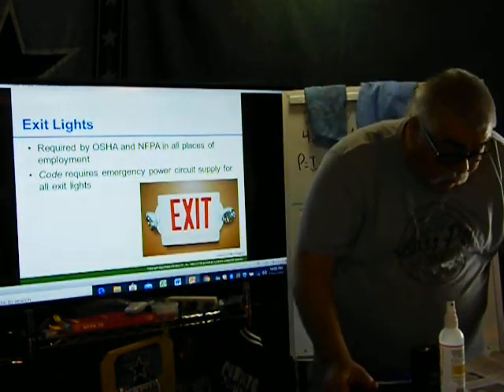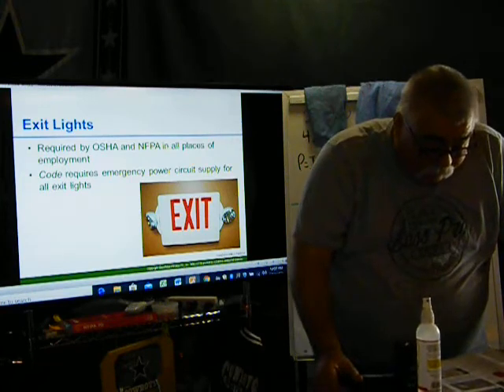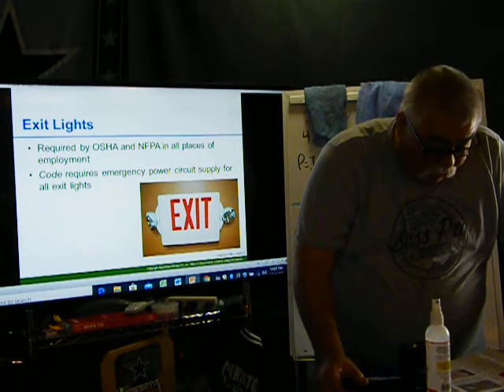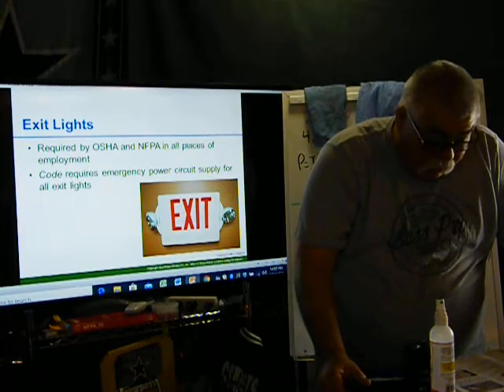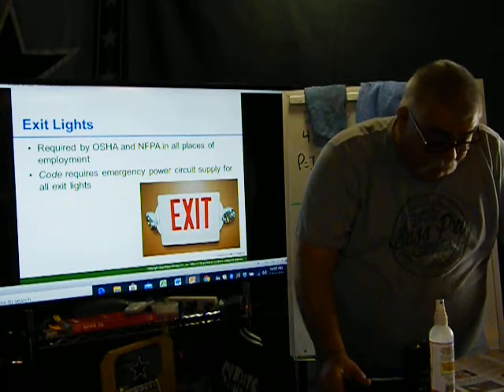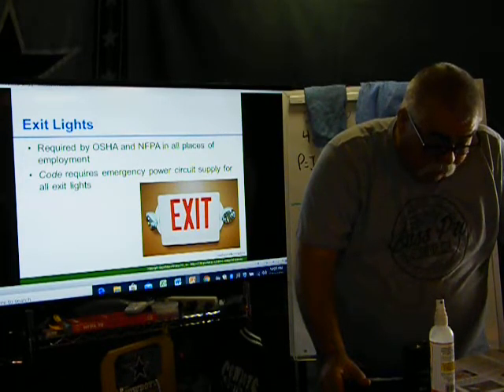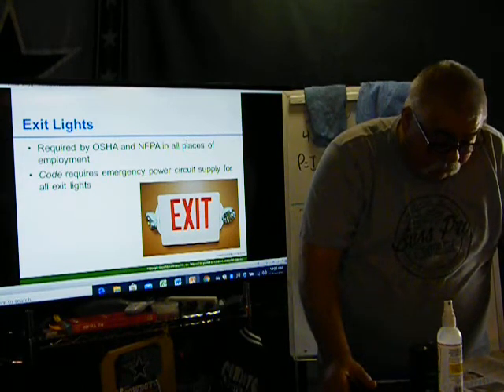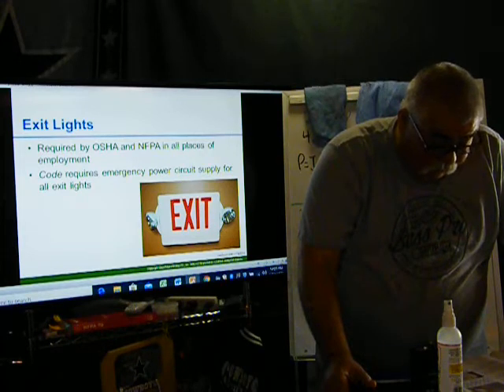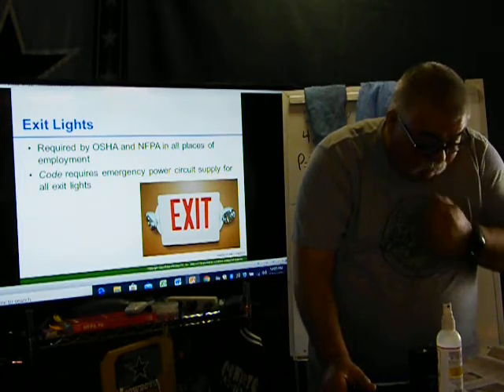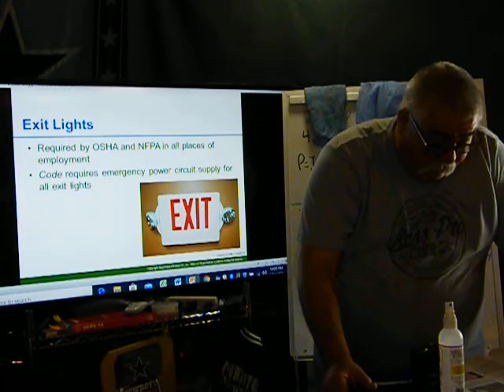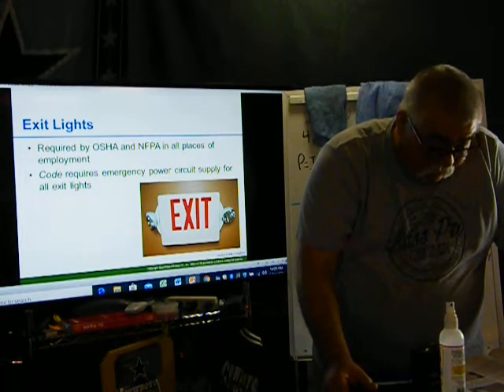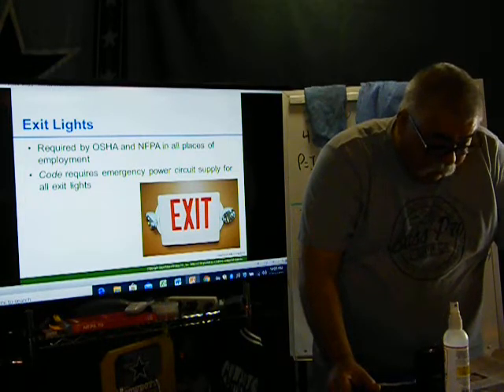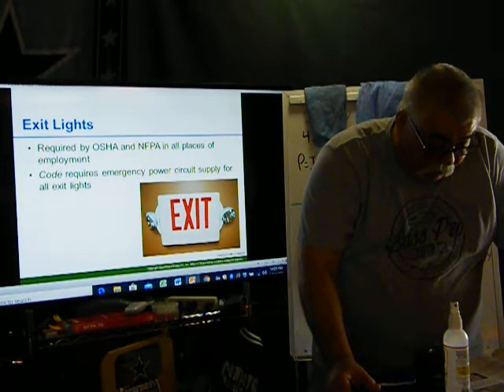On the exit side it says both OSHA and NFPA. OSHA is the Occupational Safety and Health Administration, and NFPA is the National Fire Protection Association. They have requirements for exit lights. These requirements extend to all places of employment in both new and existing facilities. Neither OSHA nor NFPA require exit lights to be supplied by emergency power. However, code considers exit lights emergency lighting equipment and requires that they be supplied by an emergency power circuit.